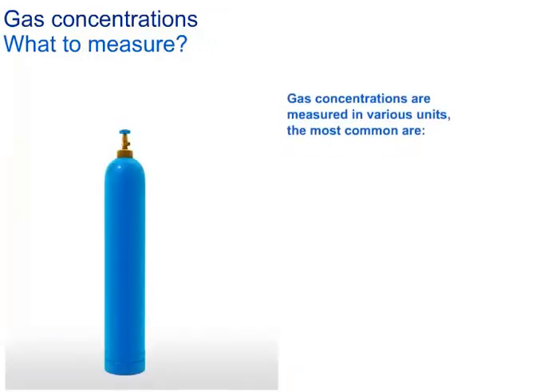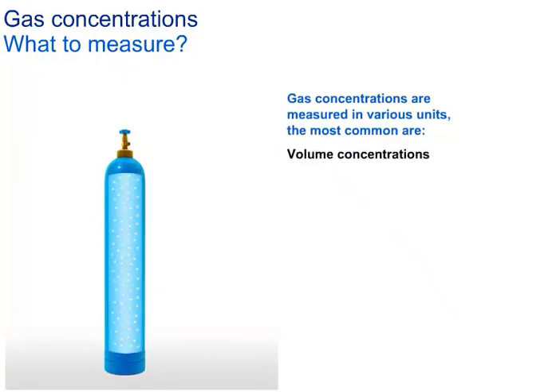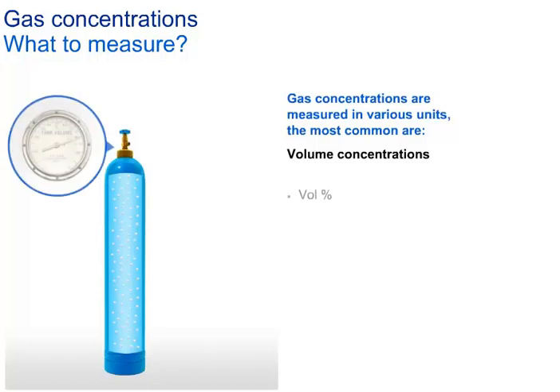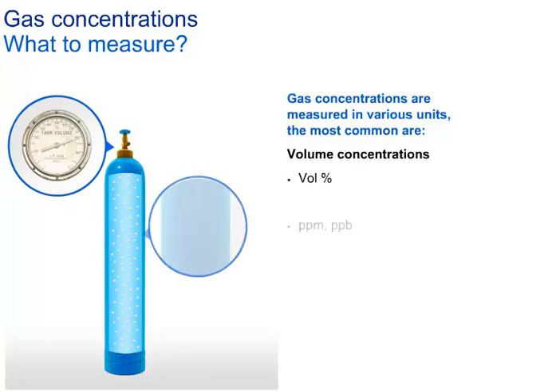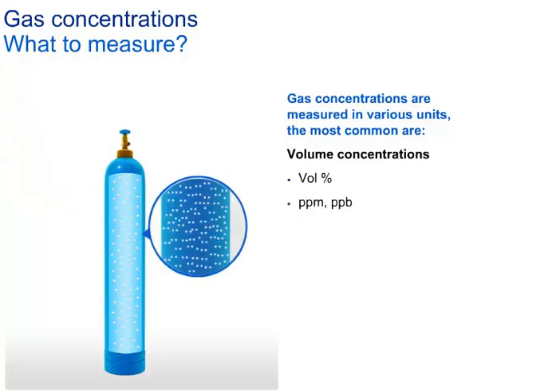These gas analyzers measure gas concentrations in various units. The most common measurements are the concentration in a volume or volume fraction. In chemistry, the volume fraction is defined as the volume of a component divided by the volume of all components of a mixture prior to mixing. The common unit is volume percent. Also very common is the measurement in parts per million, which is a number without units.